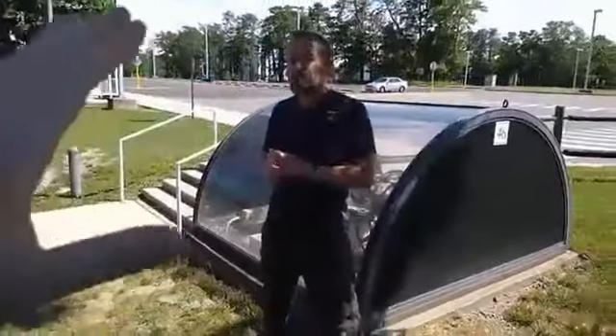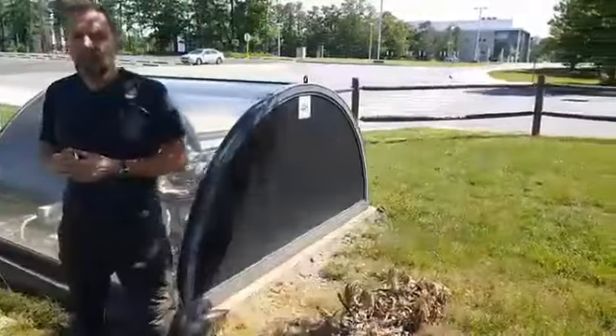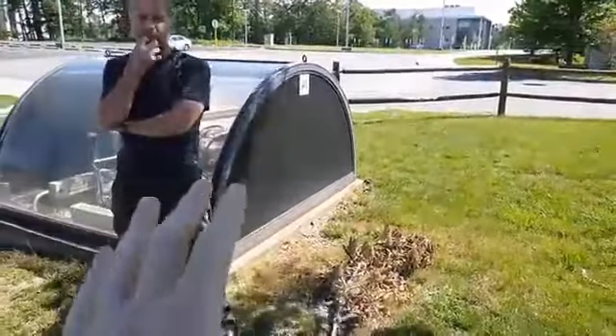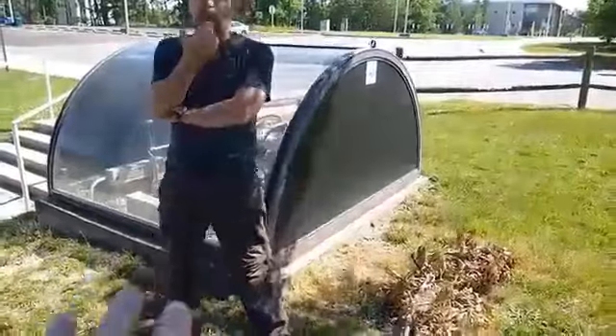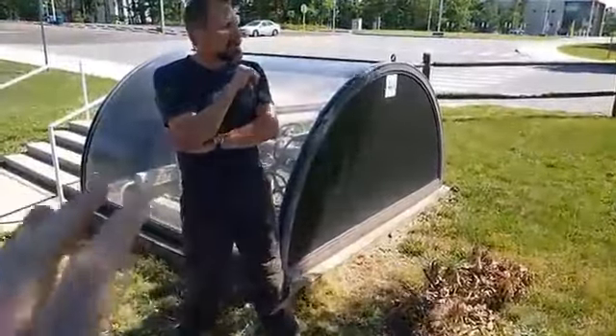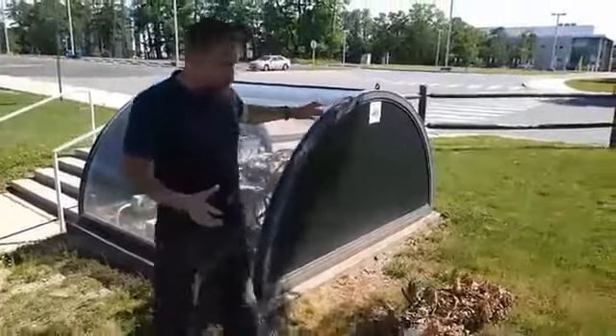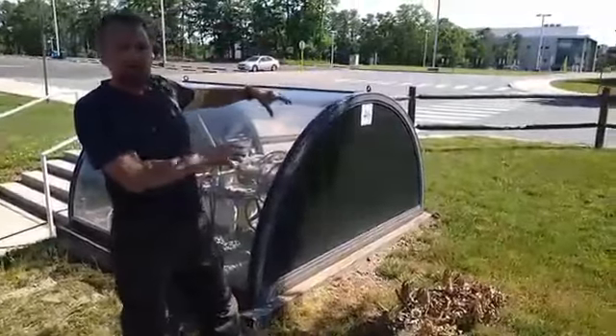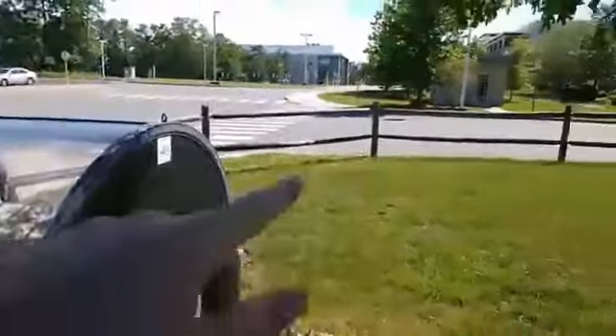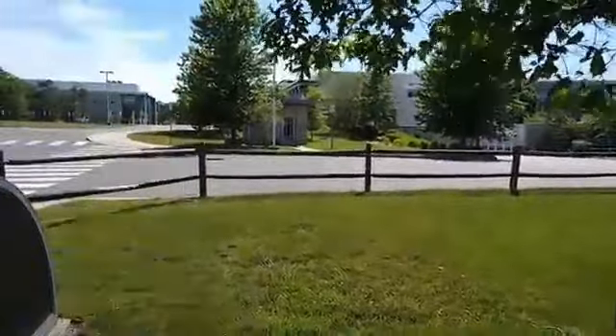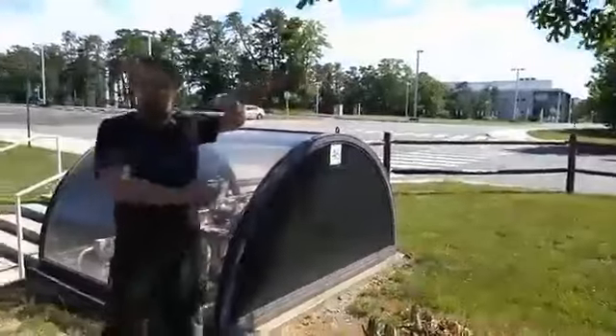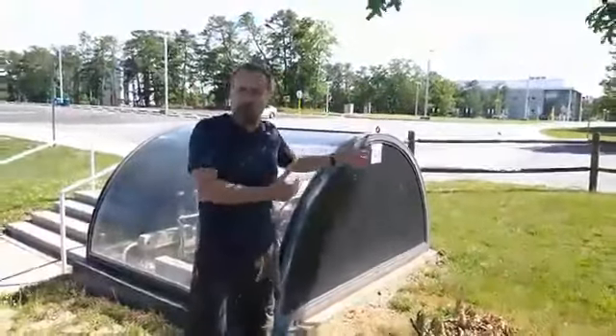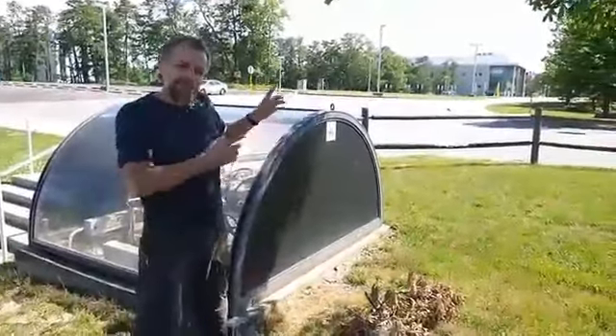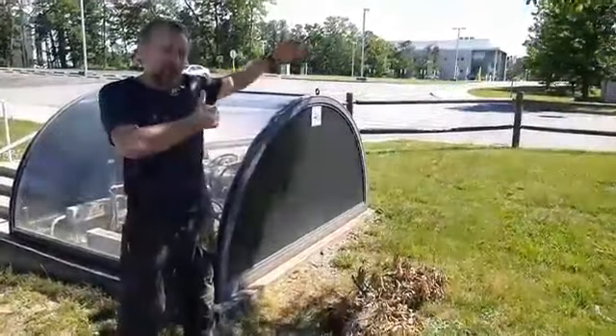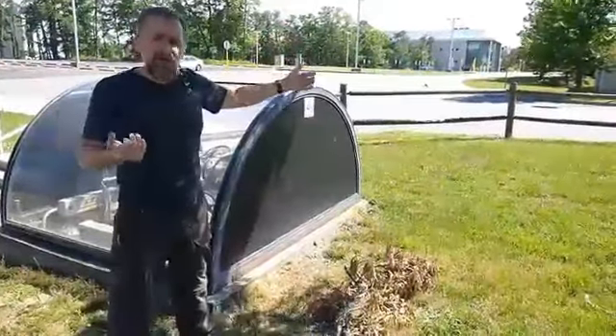You mentioned it's pumping water a far distance over. For people familiar with Stockton's campus, the aquifer we're pulling this energy from is under us in the whole area. We've got 3 wells here -- we're outside of one right now. There's another well at that building over there, and then near West Quad, or between West Quad and the campus center, there are 3 more wells. Those 3 wells are separated by about 1,000 feet -- actually it's 975 feet, so about a football field.